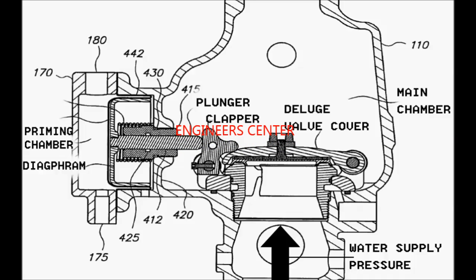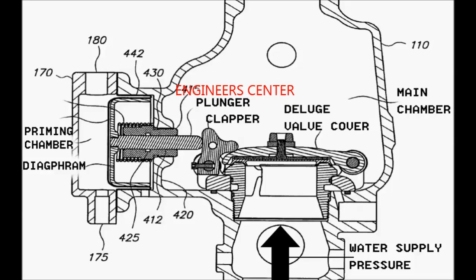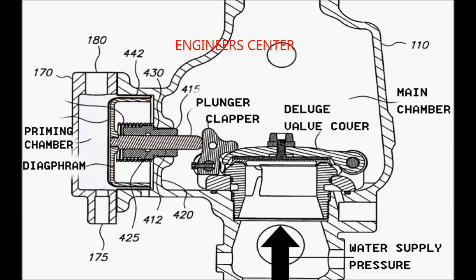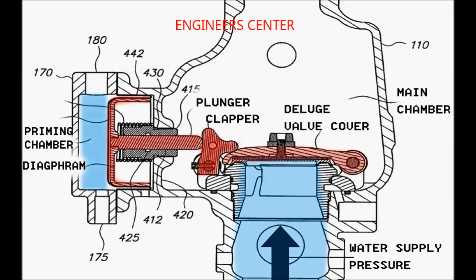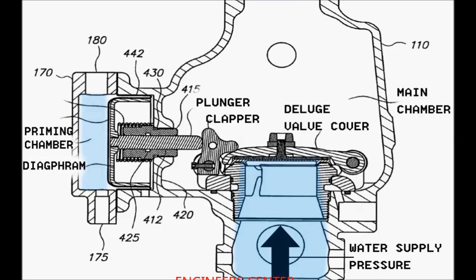The position of the deluge valve depends on the differential pressure between the priming chamber water pressure and the water supply pressure. In the shown figure, the deluge valve is in the normal closed position where the priming water pressure is pushing the diaphragm in the forward position, which is connected to the plunger, forcing the clapper to close the deluge valve cover and overcoming the water supply pressure.